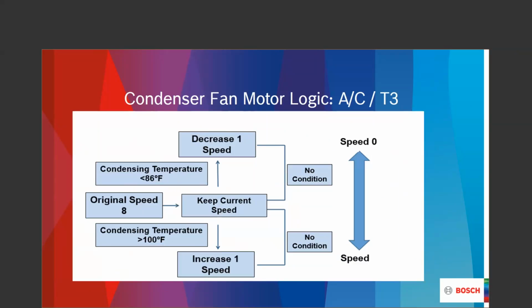And with each one of the parameter check buttons, I can push it to number 18, and I can see the fan speed. So if it's a 1.0 3-ton unit, BOVA 36, I'm going to have two parameters, high and low. So that number would be either a 4, there's your low speed, or an 8, there's your high speed. On the other ECMs, you'll actually see whatever speed you're going to have identified in that number 18.